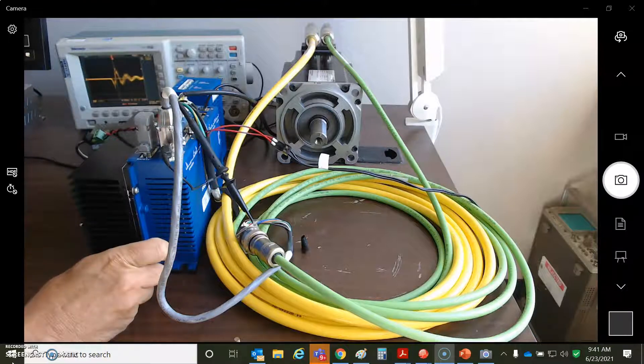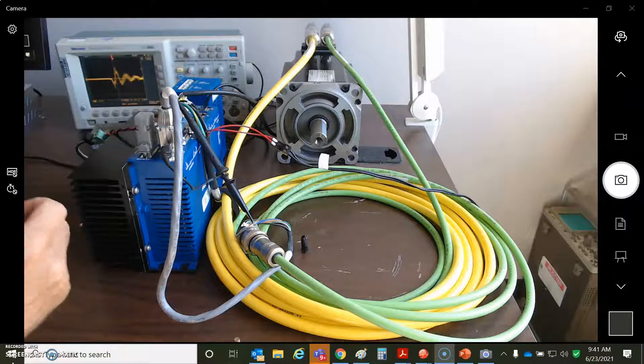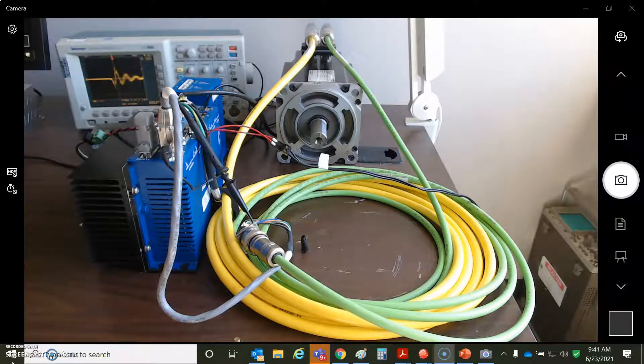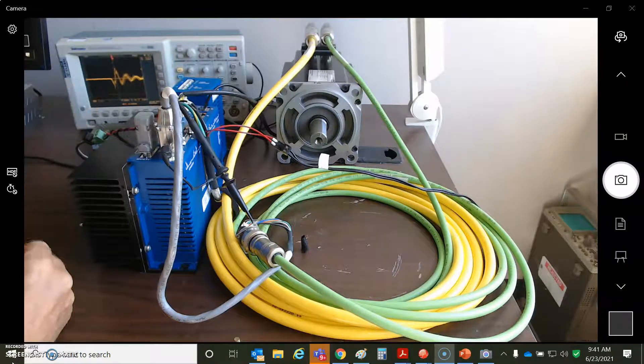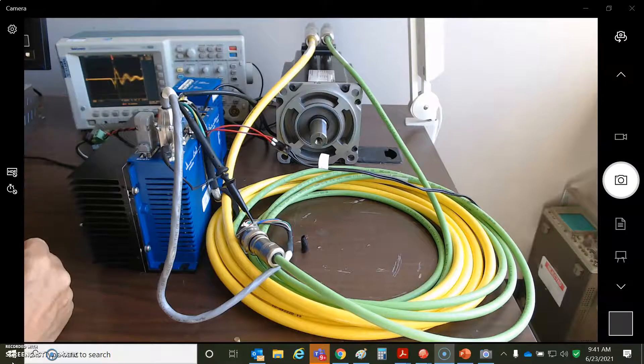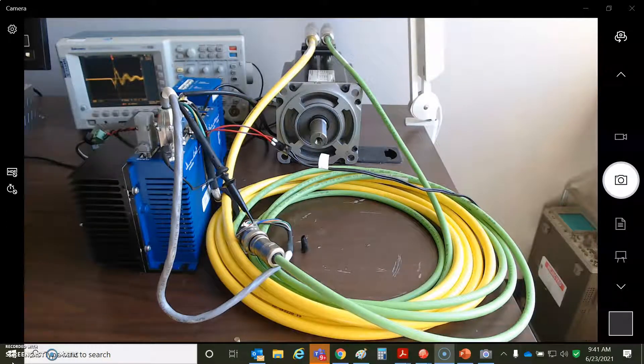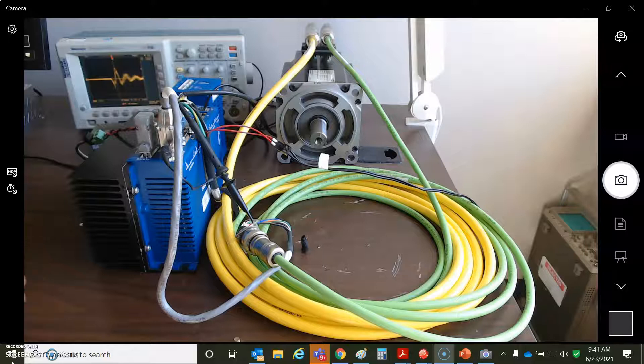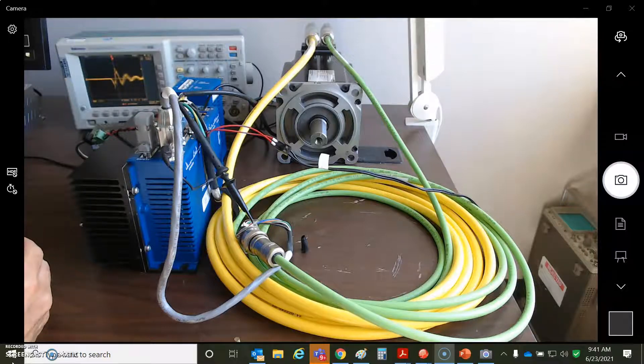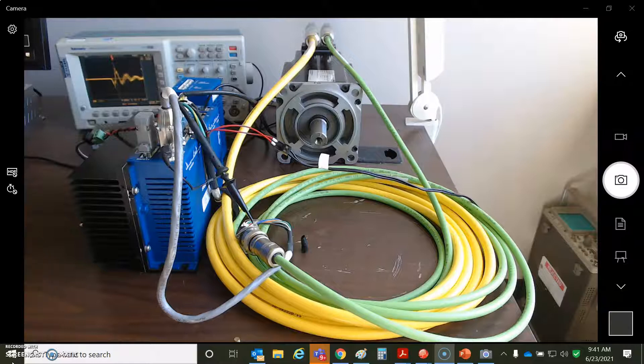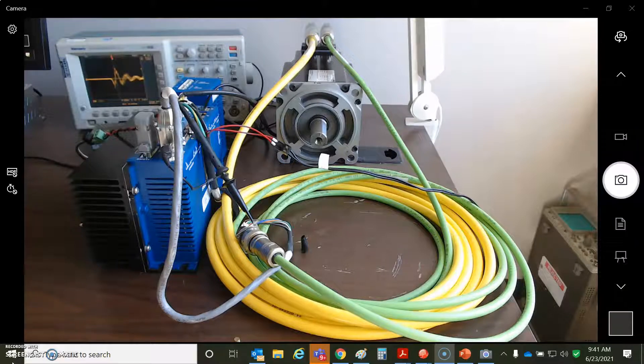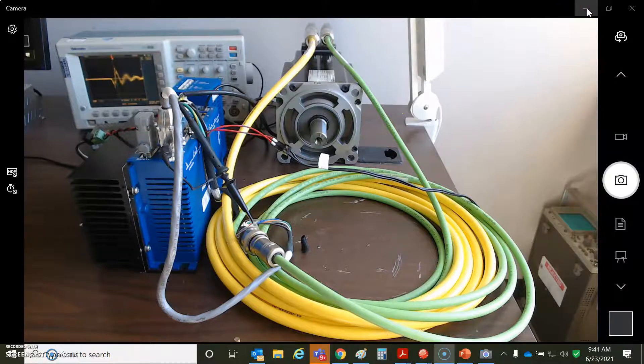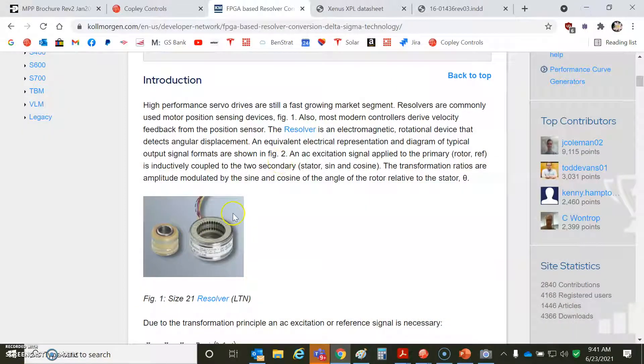And, of course, in this system, maybe the motor wasn't bolted or the Earth wasn't. We blew up the Resolver input. I've never seen this before, but I imagine that by wiring it wrong, there is an opportunity that we could damage the drive. There's always, you know, the first time ever. So that's why we're investigating this today.